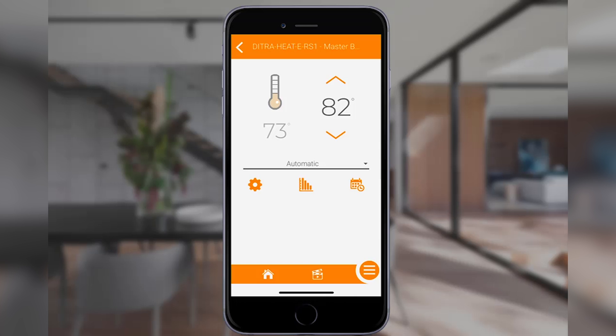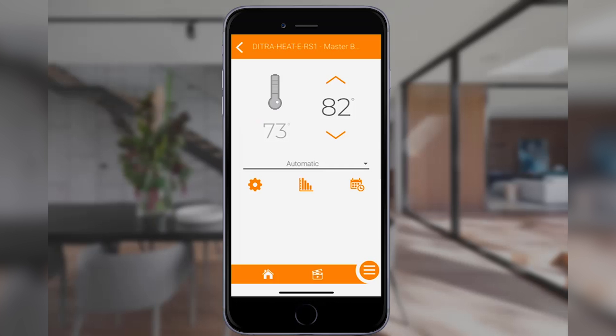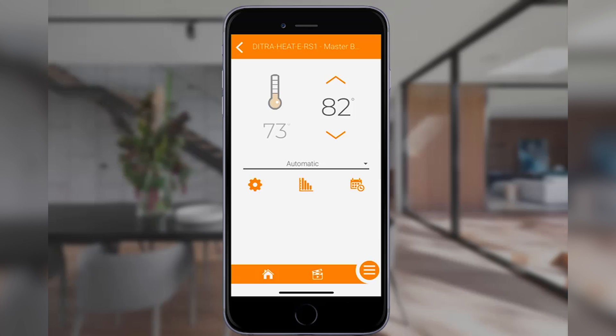At the top left of the interface you'll find the thermostat status icon. When the thermostat activates the heating cable, the icon's color will turn gray. If there is a line underneath the icon, it indicates that the thermostat is in floor mode and is sensing the floor's temperature. If there is no line underneath, it indicates that the thermostat is in ambient mode and is sensing the air temperature in the room. If the icon's color is light beige, it indicates that the thermostat is not currently activating the heating cable.